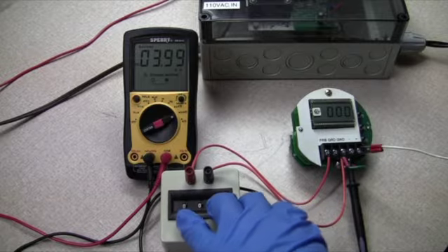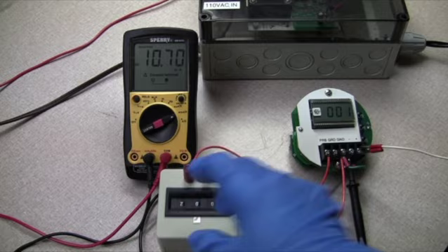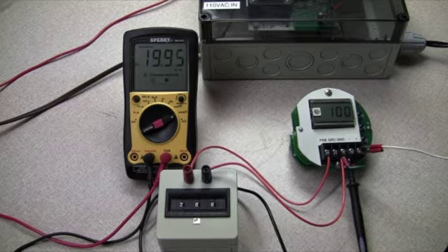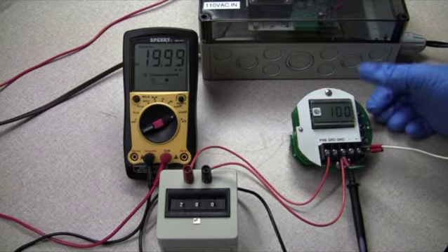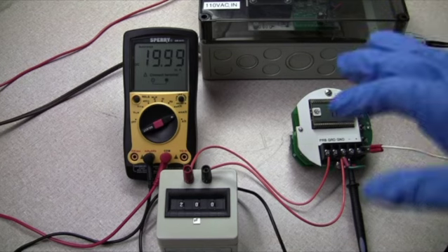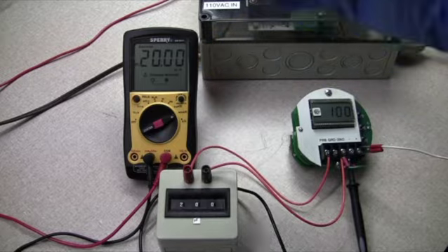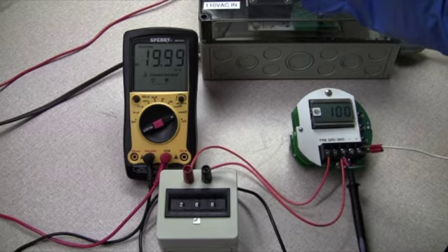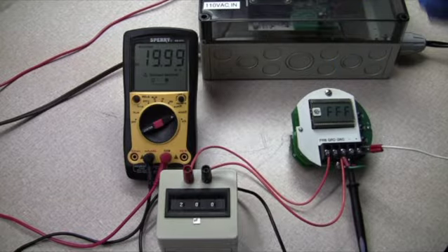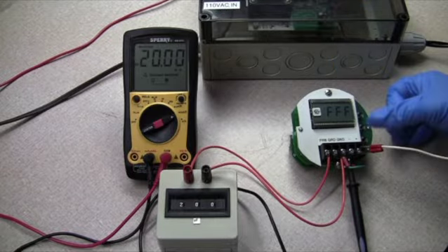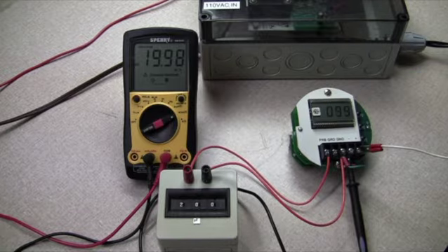Now we set the high one. We're going to bring this up to 200. We're reading 100% already, but this could be 70, 80, depending on where we calibrated at the factory to test the units. You will raise the level of liquid in your tank in the field to your desired high set point. Then you will hit the SW1 button. FFF means you're setting your full. SW3 enters. You are finished setting your high set point.